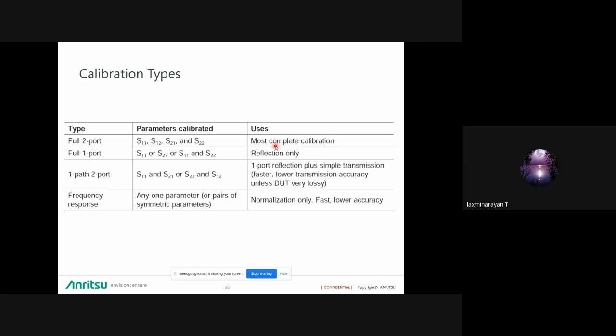So now we will talk about antenna measurement using the VNAs. We have a 1-port VNA, because, as we discussed, the antenna measures only the reflection parameters. So for a reflection parameter, a 1-port network analyzer is sufficient. For the 1-port network analyzer, we have the MS46121B, which goes from 150 kilohertz to 6 gigahertz with an N male connector, which connects directly to the port, device, or antenna cable, and it is handheld, so you can hold it in your palm. What is the requirement for this? It works from your external PC or laptop with Windows 10, Windows 7 or 8. Using a USB cable, we connect it to the PC, and we can use the MS46121B with the ShockLine software.